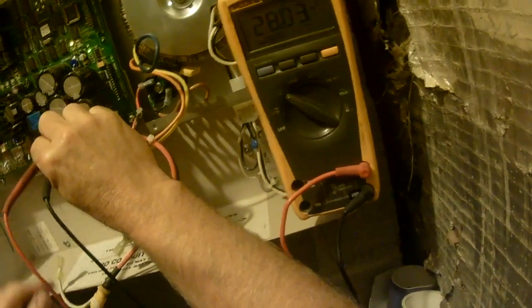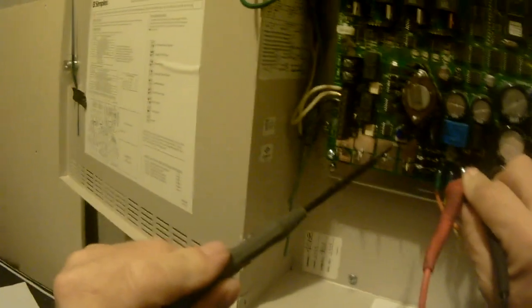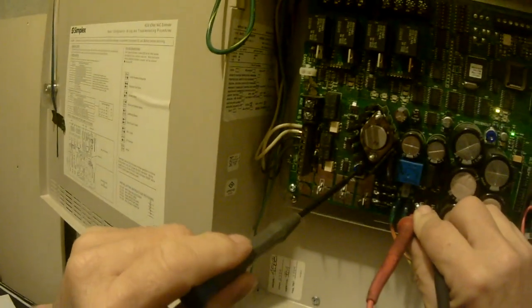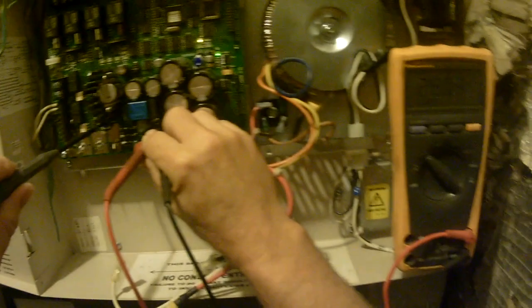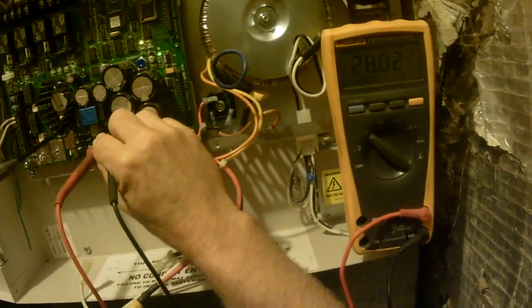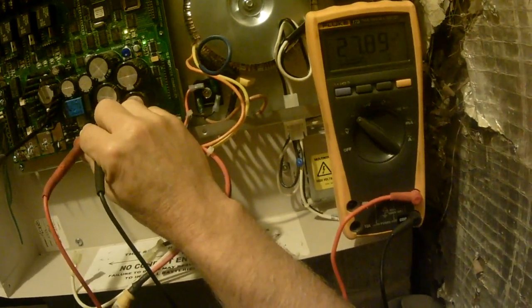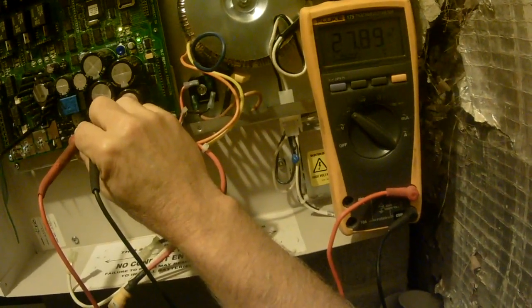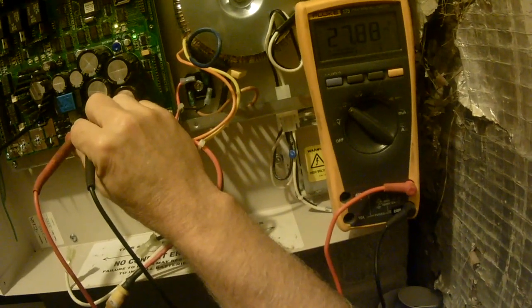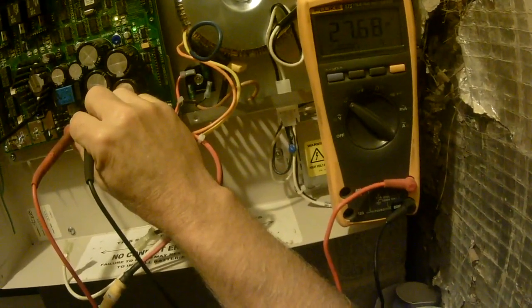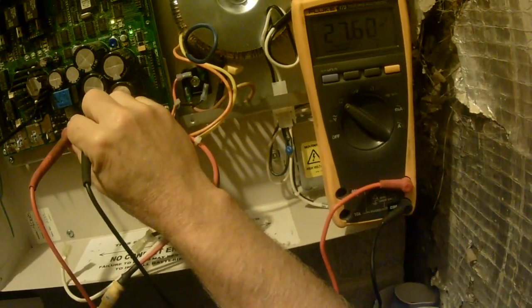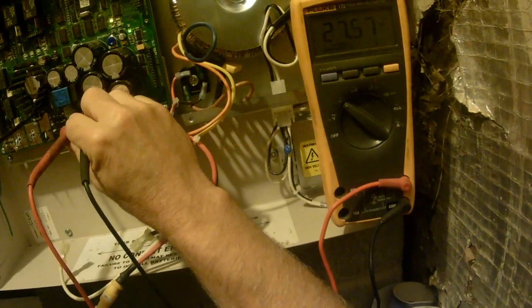Sometimes you check this and it doesn't say anything. This one here says 28.03. Now that's a little bit high, so there's a little adjustment screw down here. It's the charger adjustment, and I'm going to adjust that and bring this thing down to the factory recommended setting of 27.6.